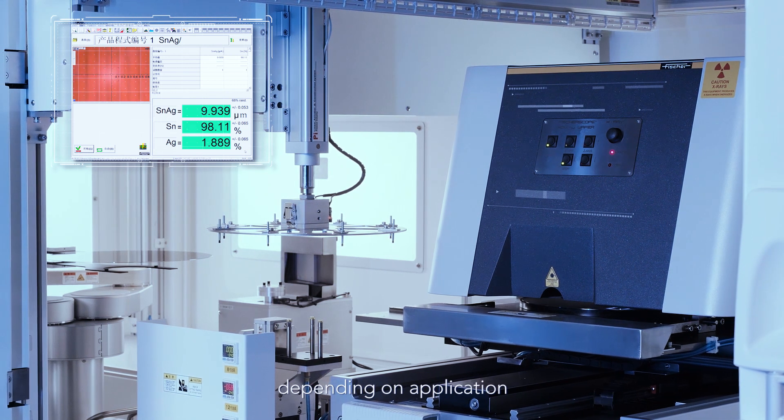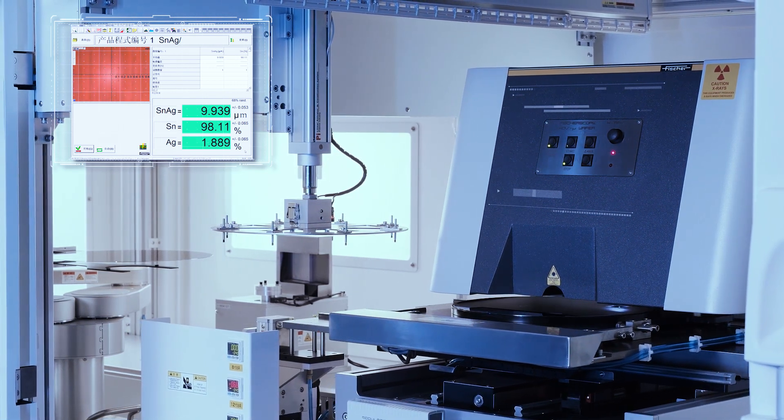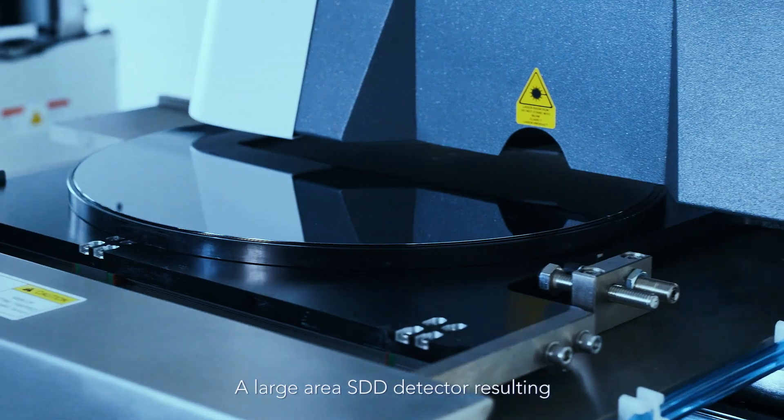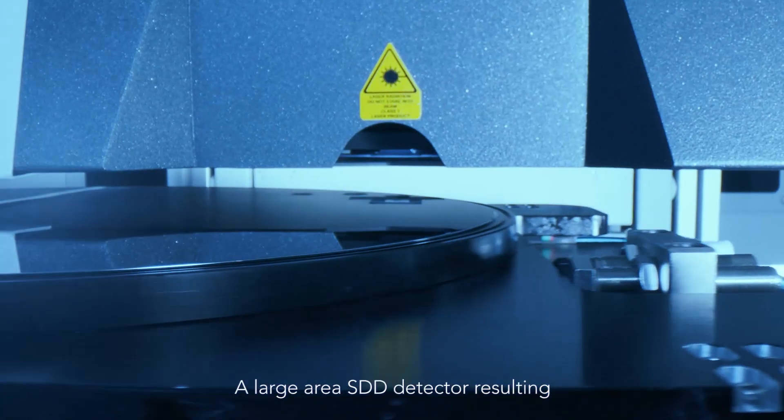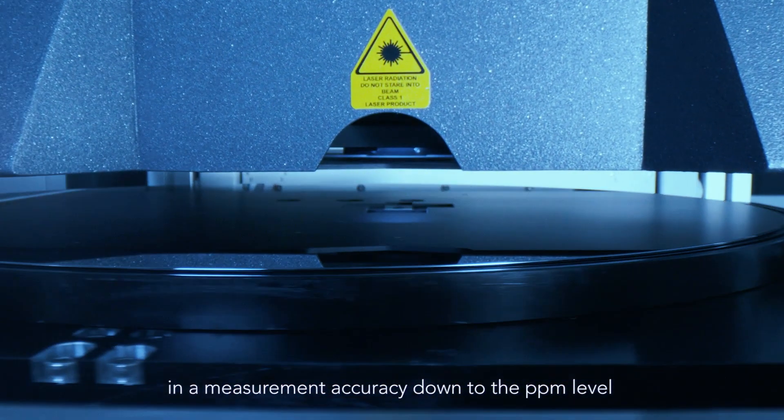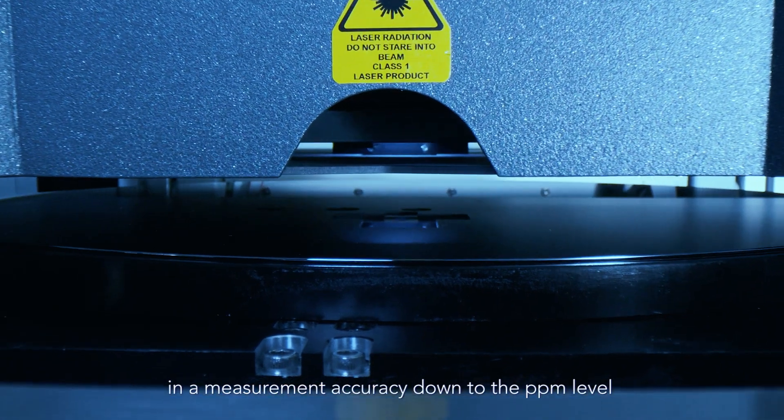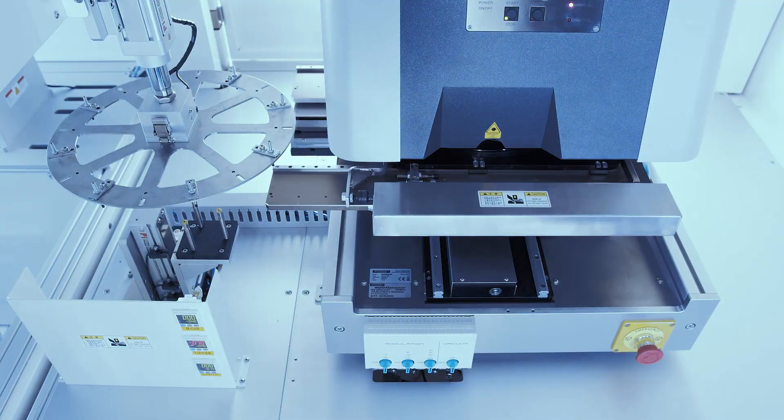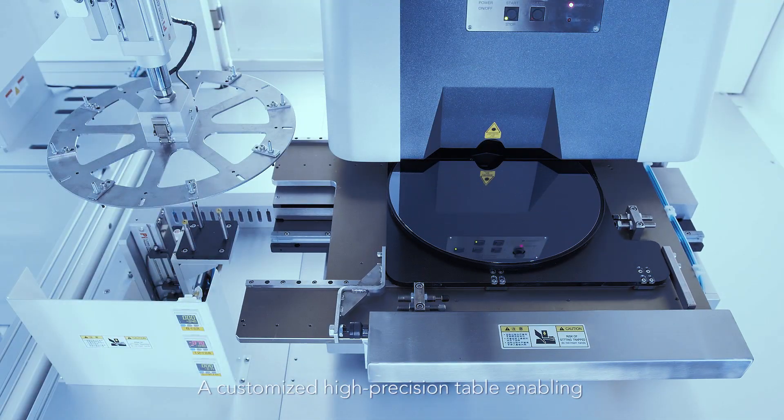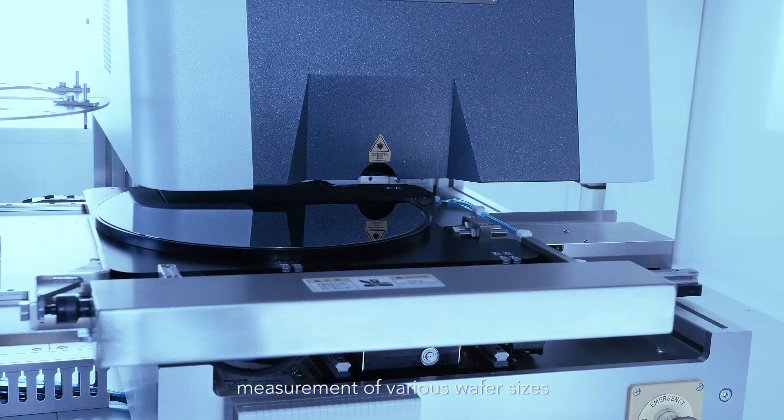Other features include a large area SDD detector resulting in measurement accuracy down to the PPM level, and a customized high precision table enabling measurement of various wafer sizes.